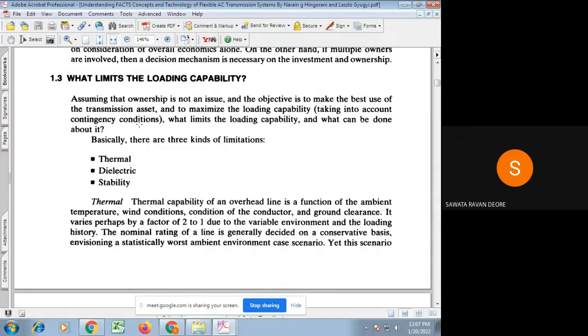Thermal rating means we can say the electrical power rating of a transmission line. Why is it called thermal rating? Because the electrical power handled by the transmission line is decided by how much current rating it has and how much operating voltage rating it has. When we say the transmission line has some ACSR conductor, the material of the conductor, say aluminum, and the size of the conductor offer some resistance. That is R = rho L / A, where rho is the resistivity of the material, L is the length of the total transmission line conductor, and A is the cross-sectional area of the conductor.